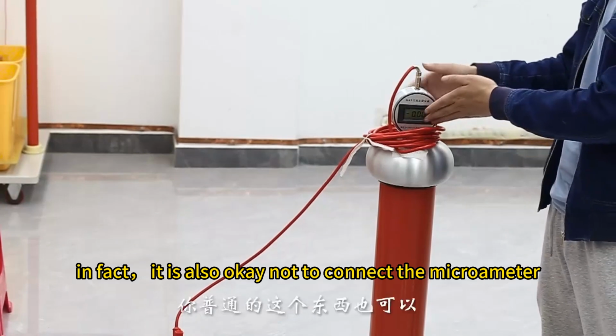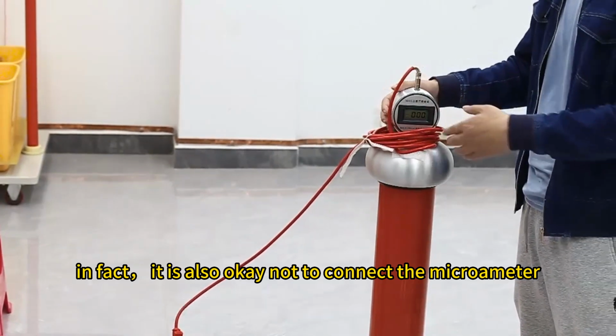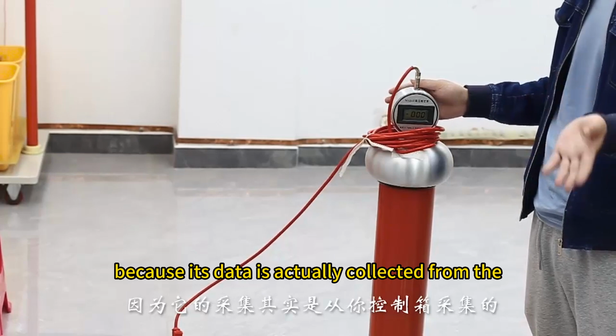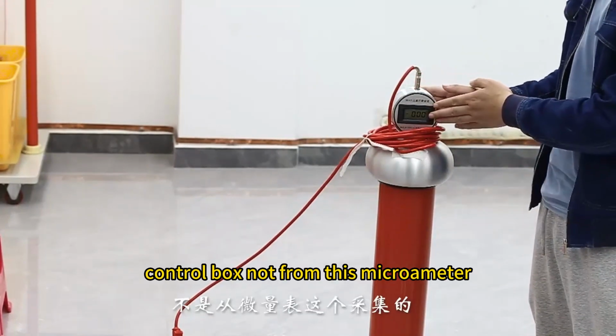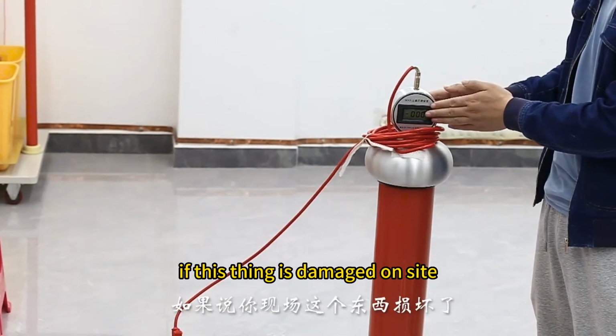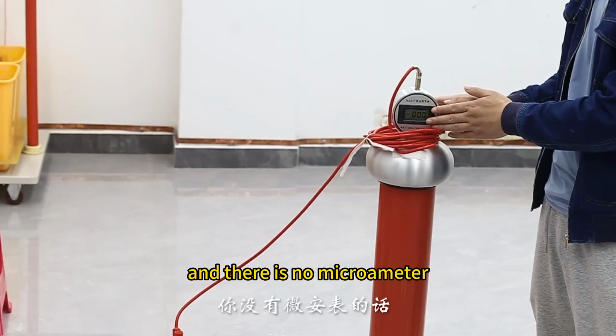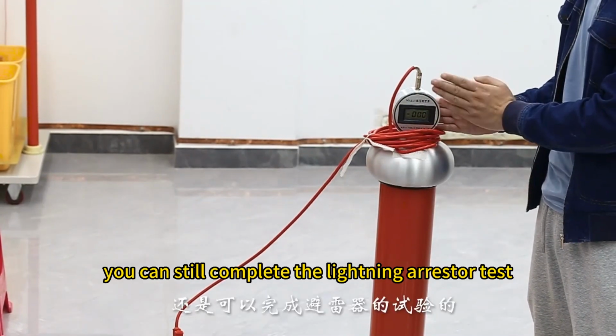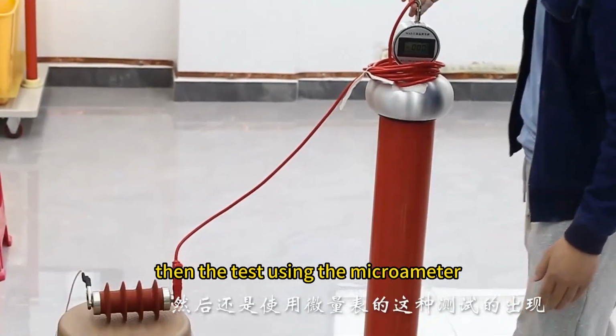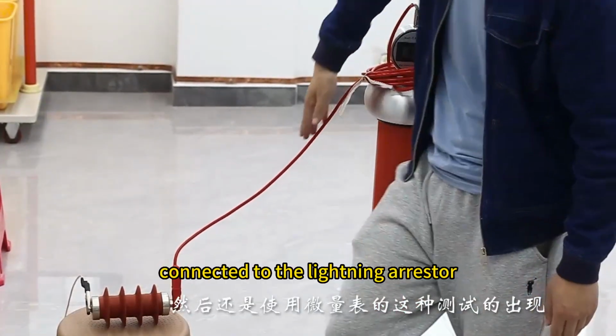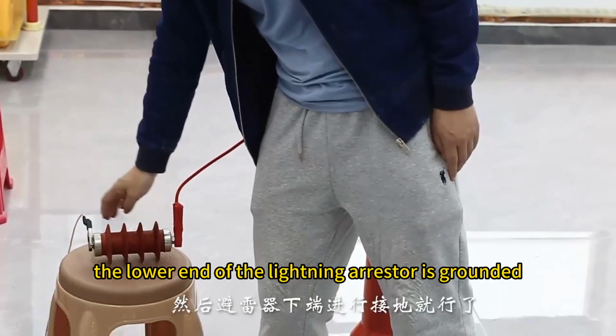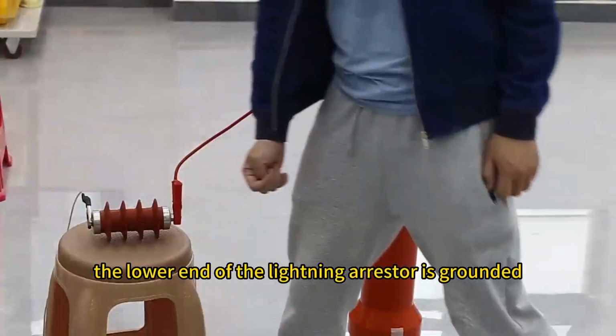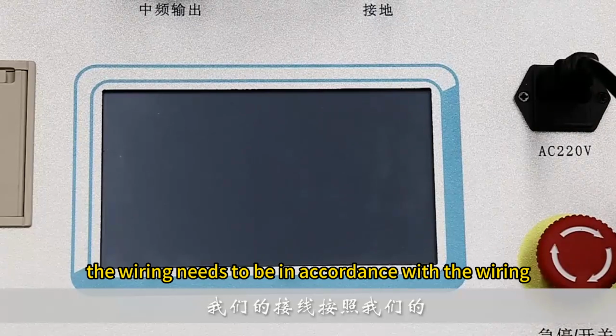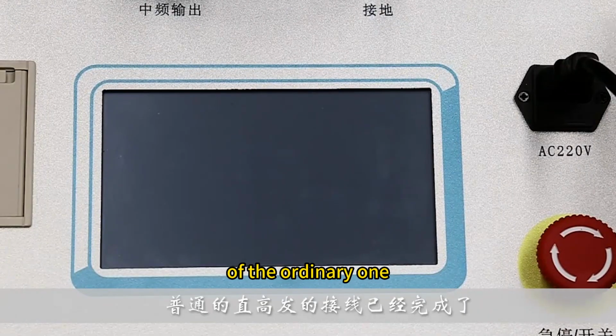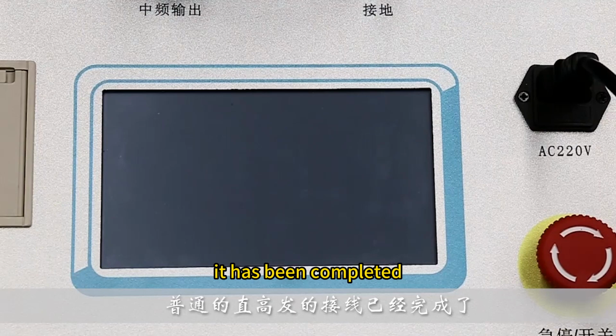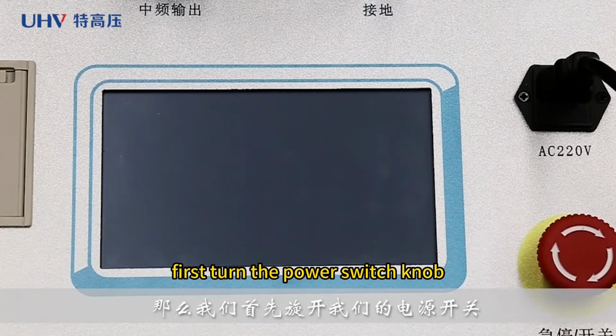In fact, it is also okay not to connect the microammeter, because its data is actually collected from the control box, not from this microammeter. If this thing is damaged on site, and there is no microammeter, you can still complete the lightning arrestor test. Then the test using the microammeter is connected to the lightning arrestor. The lower end of the lightning arrestor is grounded. The wiring needs to be in accordance with the wiring of the ordinary one. It has been completed. First turn the power switch knob.